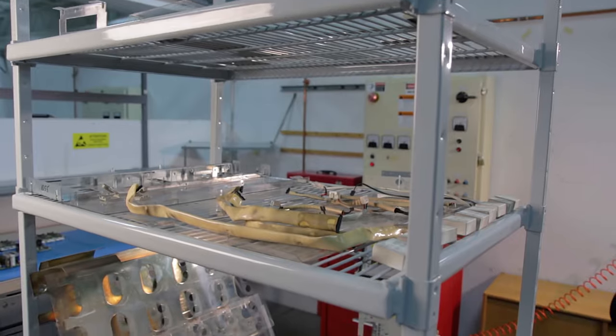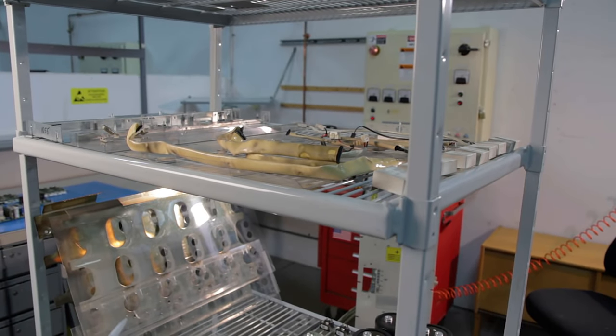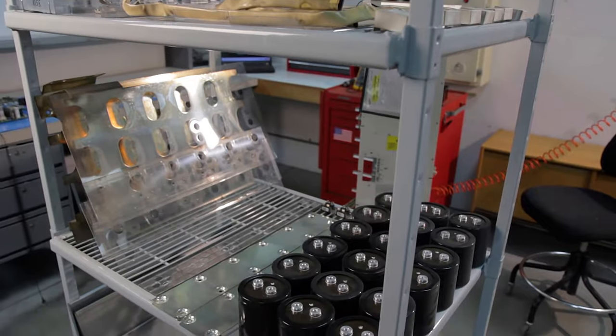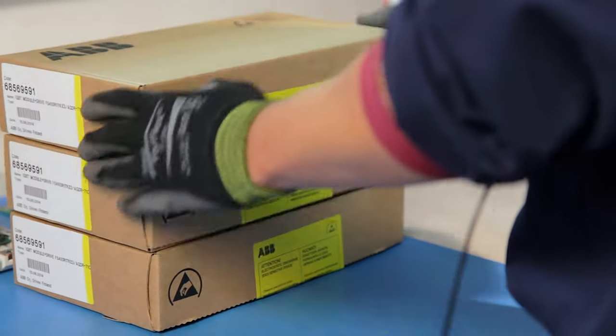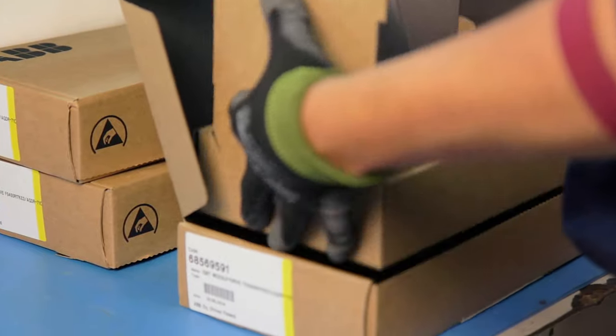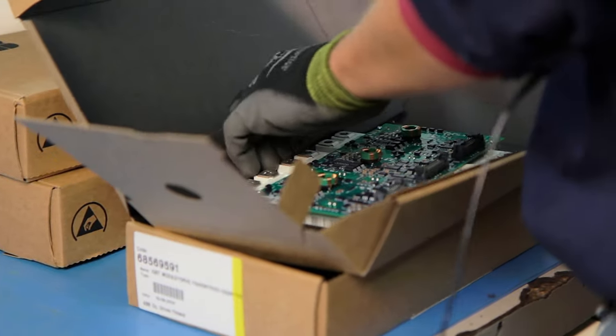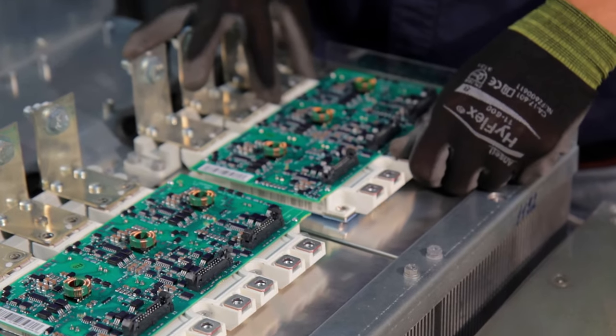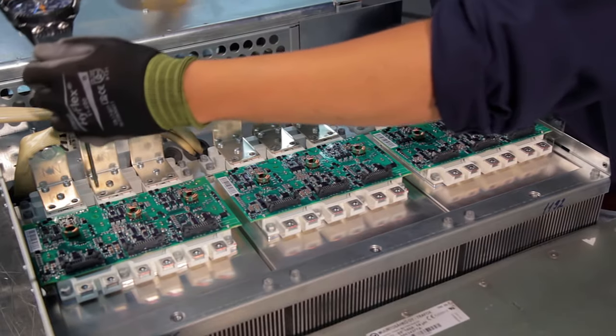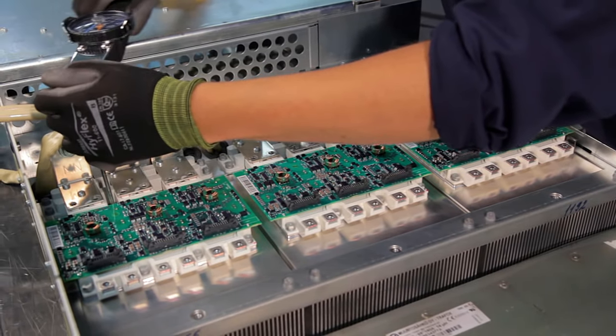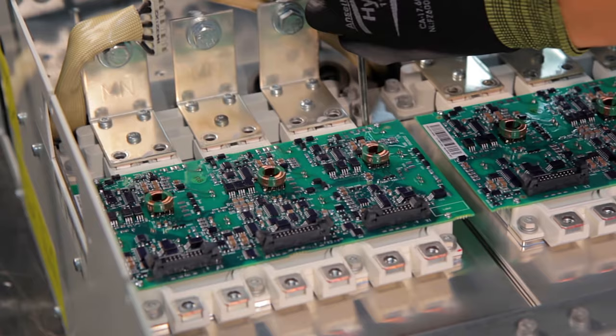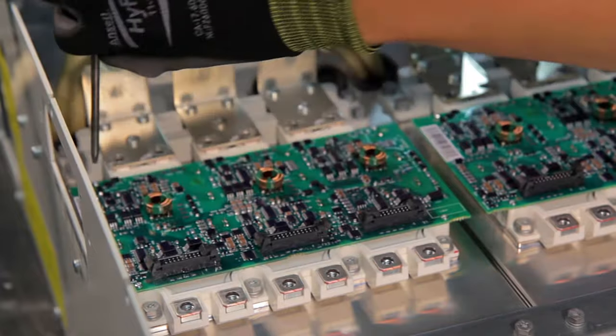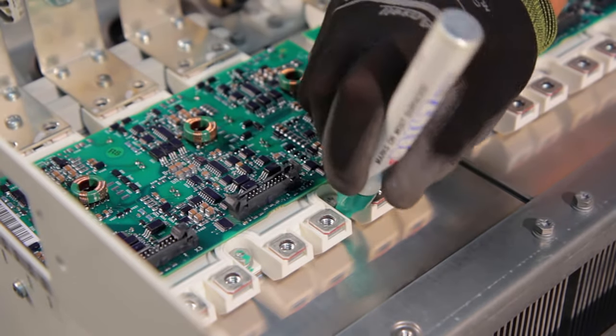All materials are dried after the cleaning process has been completed and the drive is ready for the repair and assembly process. During the repair service, any defective components are replaced with new genuine ABB parts and the drive is reassembled. At this point, additional circuit analysis is performed to isolate and identify any other marginal or aging components. Afterwards, all power connections are verified for proper torque, per ABB specifications, and marked.